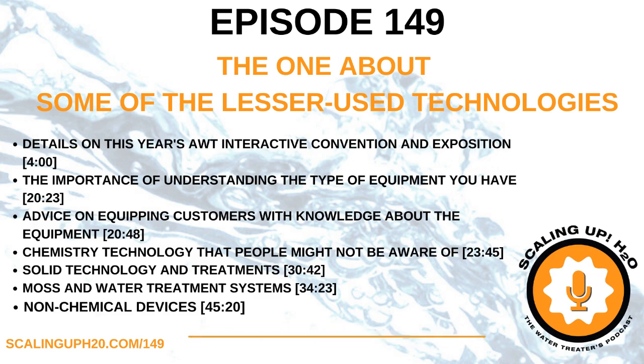I won't mention any product names, but there's a phosphonium-based biocide that we were one of the first to do some beta testing on, and we had a PVC end, and we thought somebody came in there with a hammer and just broke all the heads. I've had the exact same thing happen to me. So make sure you're looking at your compatibility charts, and there's a lot of them out there. I think every manufacturer has a compatibility chart, so that should be the first thing you're looking at before ordering a pump.